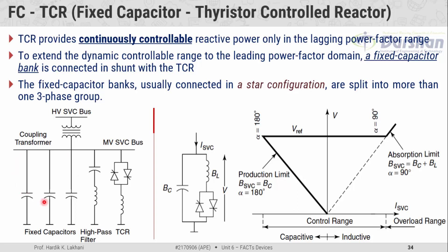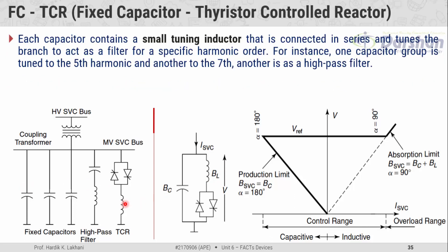The fixed capacitor banks are usually connected in star configuration and are split into more than one three-phase group. In the equivalent circuit diagram, one branch represents the net susceptance offered by all capacitive branches, and the other branch represents the susceptance offered by the inductive branch. Each capacitor contains a small tuning inductor connected in series that tunes the branch to act as a filter for a specific harmonic order — for instance, one capacitor group is tuned to the 5th harmonic, another to the 7th, and another as a high-pass filter.